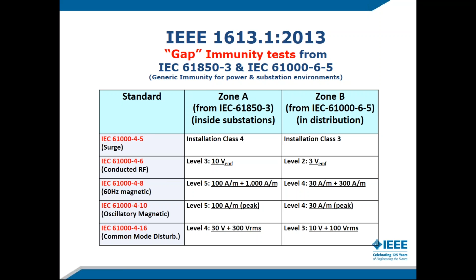So the gap immunity tests that were not in that list, you can see the numbers that were picked up there. Conducted, for example, is 10 volts. And the 60 hertz magnetic is 100 amps per meter, all the way up to 1,000 amps per meter, and so forth. And these are not uncommon, but some might say that 30 volt number for the common mode disturbance is pretty much on the high side. But again, you're in a very difficult and severe electromagnetic environment inside the substation grounds.